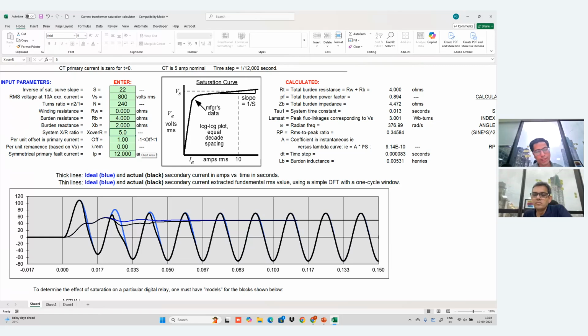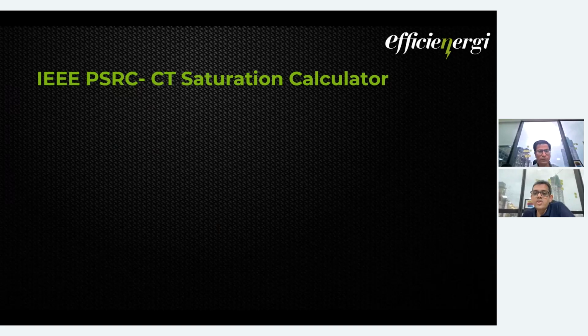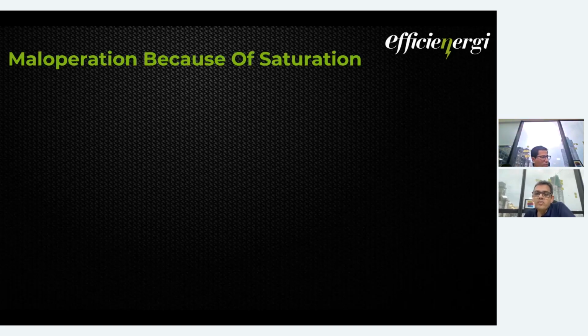So the short circuit study, till now we were using mainly for the device duty, but this is one use wherein you understand the worst case fault, the X by R, and the asymmetry which is going to be there in your distribution, and accordingly you can design your CTs. It's a very important area which designers, especially design consultants, can take into account. We are not sure we have seen this level of detailing being done by a lot of consultants, but for projects with mission criticality, it can definitely be taken as an input much earlier, working on the short circuit calculations during the design phase, and giving manufacturers the way in which the CTs are to be designed and manufactured.